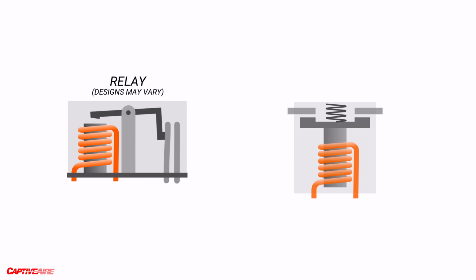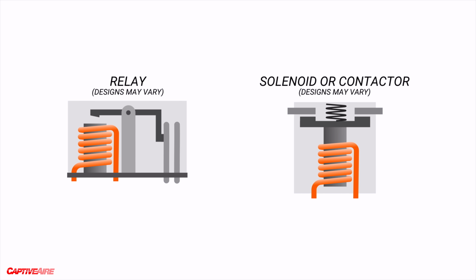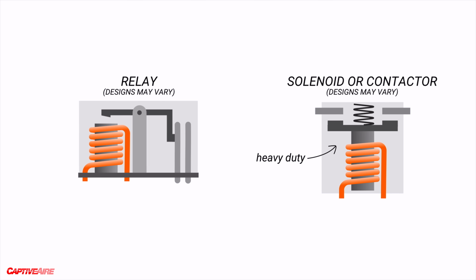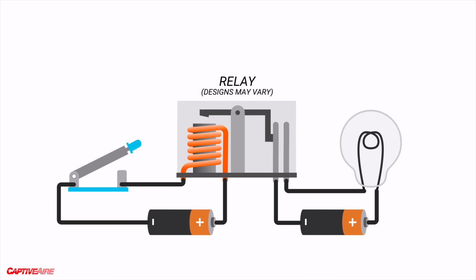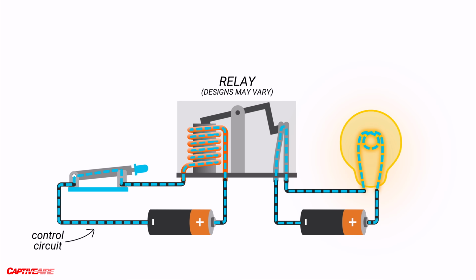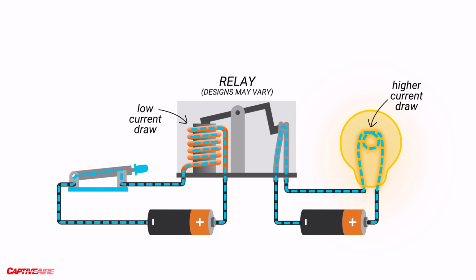Solenoids and contactors do something very similar but are designed to handle much larger loads. But how are these different than a switch other than being pretty fast? Well, notice that the circuit used to control the relay, solenoid, or contactor is separate from the circuit actually energizing the load. This can be a huge benefit. It may only take a tenth of an amp to power up this electromagnet, while the load it's controlling takes 10, 100, or even more.